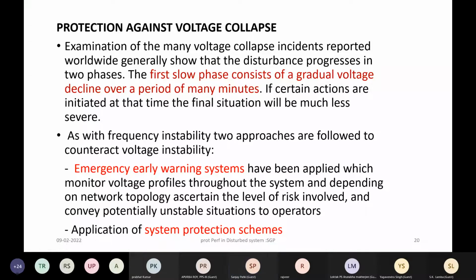So there is an early warning system at the load dispatch centers, which will alert the system operator to take corrective action as the margin becomes smaller. That means the margin of stable operation for the voltage collapse, on the PV curve, much before the nose point approaches. The nose point is like the knee point voltage of a magnetic core. So before the nose point is reached, there is normally sufficient time to take corrective actions. And that is basically the role of the system operator when the early warning alert is provided for the critical system behavior.